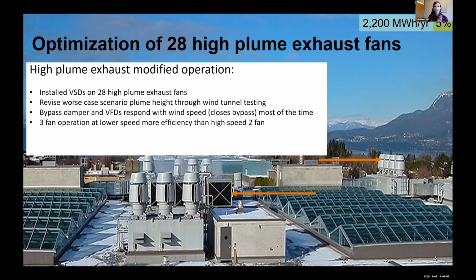Another project that we worked on, and we've worked on this one on a number of buildings, not just life sciences, is the optimization of 28 high plume exhaust fans. These are strobic fans that run basically 24/7 to provide or exhaust the air that's needed in our laboratory buildings. And what we did is we hired a consultant to do wind tunnel testing of this building and review the worst case scenario for plume height requirements. And basically what we were able to do is adjust the maximum plume height that the strobic fans were exhausting air to, while at the same time also closing bypass dampers.